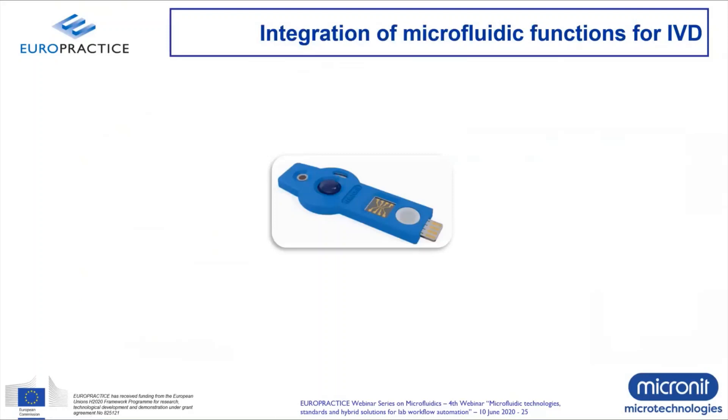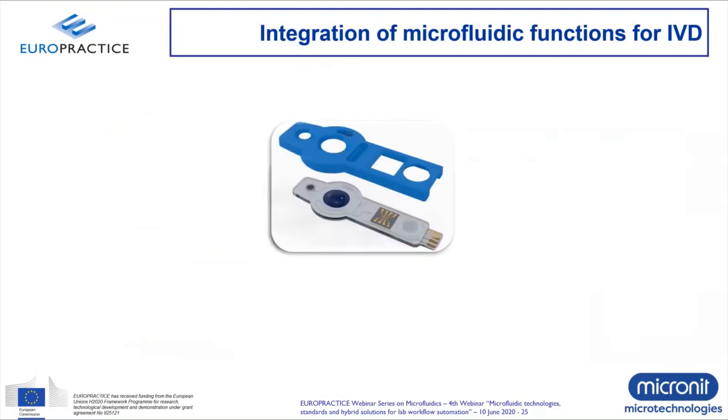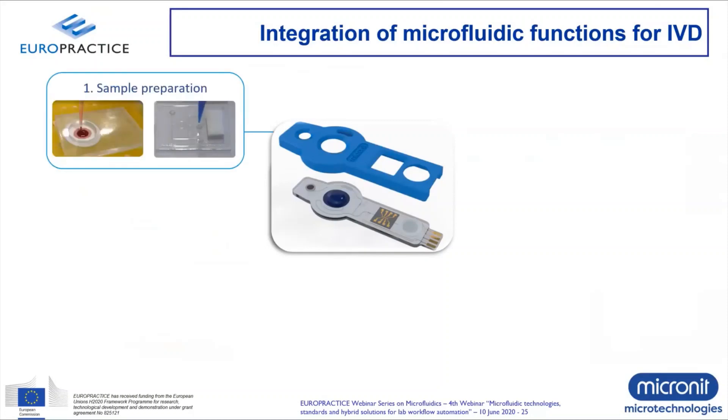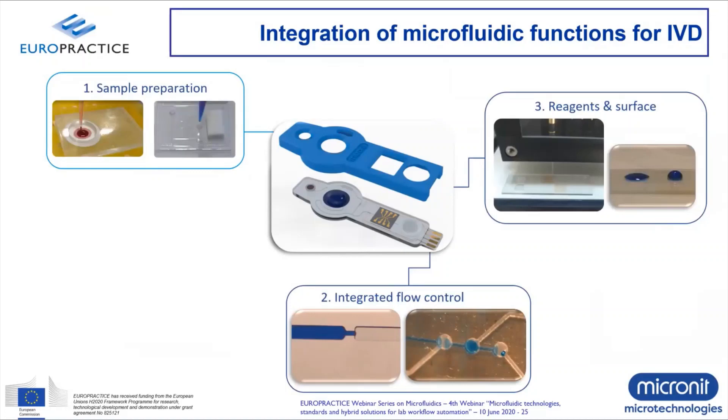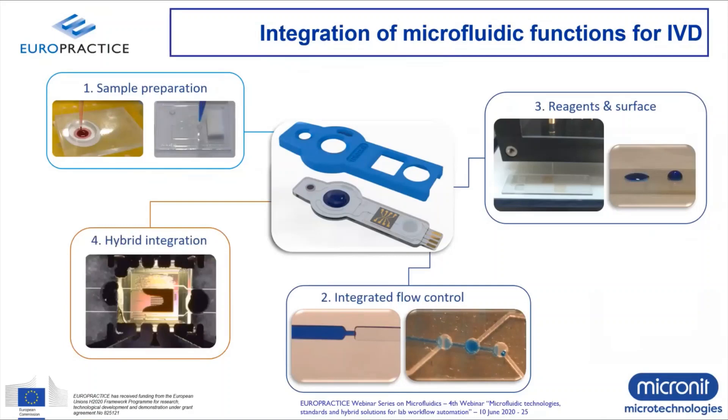Let's take an IVD cartridge as an example to see what aspects are relevant when integrating microfluidic functions. First, sample preparation: we need functions to prepare the sample for measurement or detection — things like filtration and volume metering. We need some kind of flow control, whether passive or active, to move fluid through the device in a controlled way. We need reagents and surface functionalization to ensure biology runs properly and there's no unwanted adsorption to the surface. Finally, we need some kind of sensor or detector integrated into the cartridge to perform the measurement.